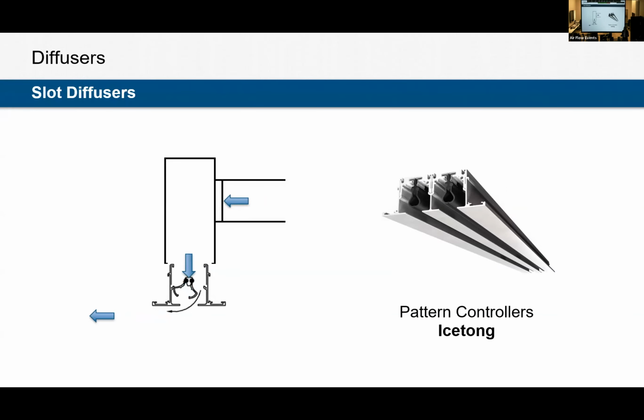And then there are slot diffusers with variable control patterns. This slot diffuser image here is a 2 slot. If we put that against a wall, we could have one slot washing the window and running down the wall, and the other slot directed out across the ceiling. So you've got some variability there when you have more than one slot. And you have the variable pattern controllers. We know that the contractors all set these pattern controllers, job specific every time. Yes, they're perfect. They're perfect.